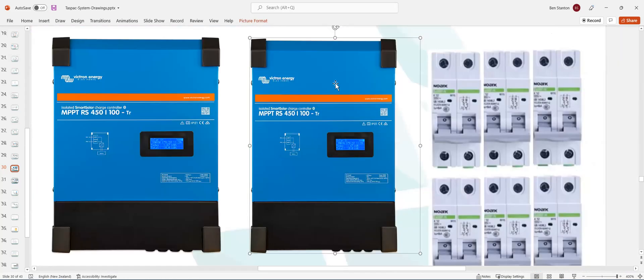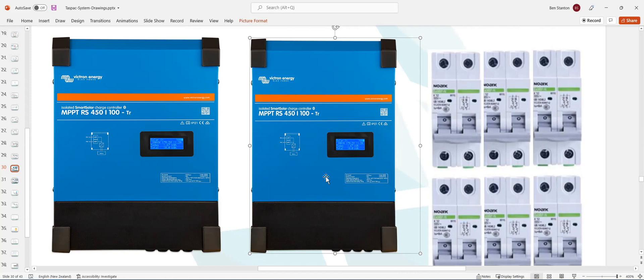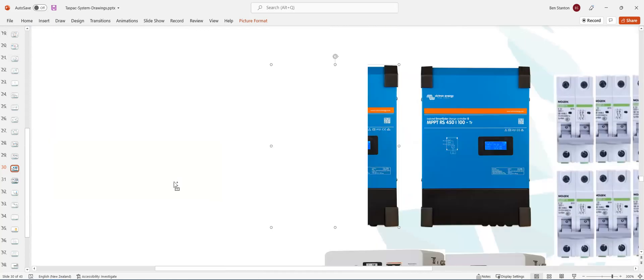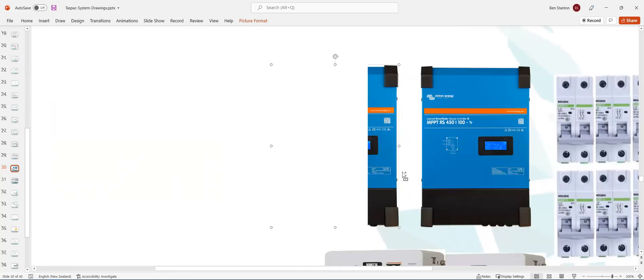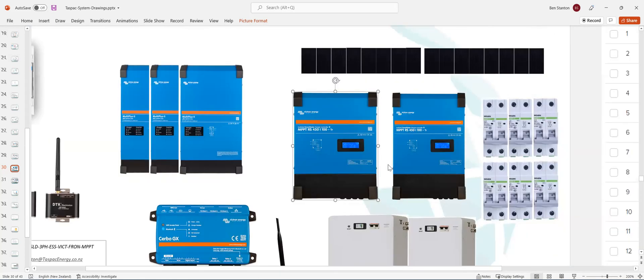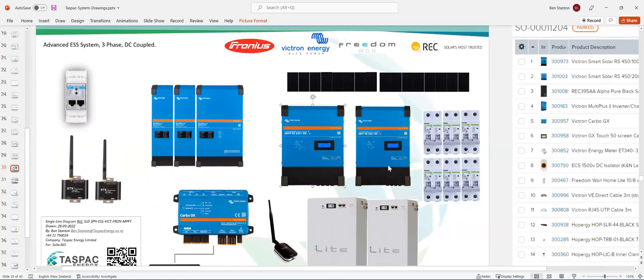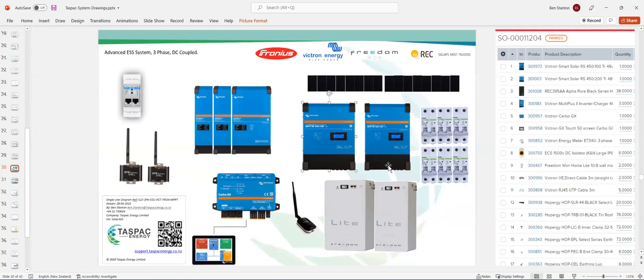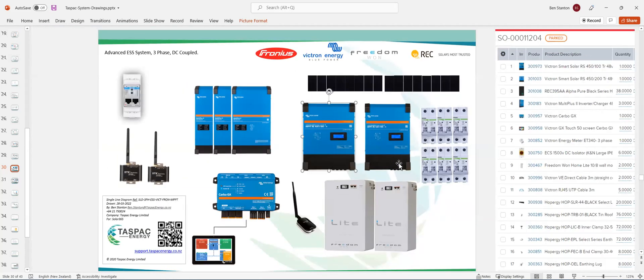Each MPPT has two. Well, sorry, the MPPT 100 amp unit has two string trackers. And the 200 amp unit has four string trackers. And each string can go up to 450 volts. So normally that's sort of seven or eight panels per string. Let's go down to the wiring diagram and see how all this fits together.